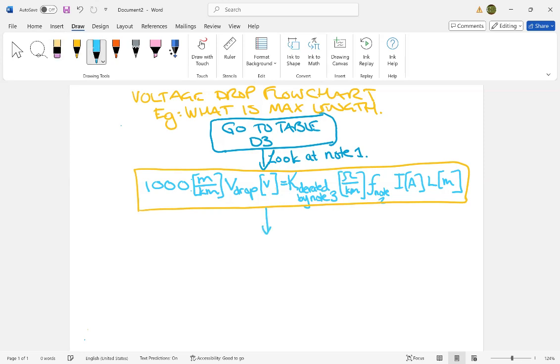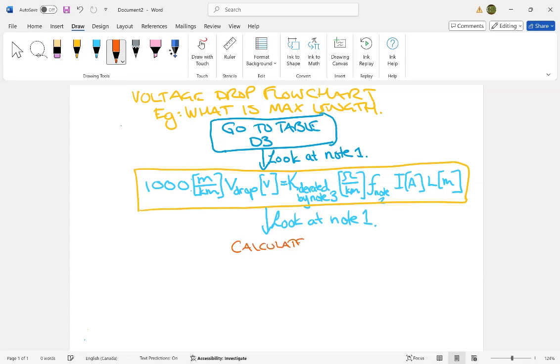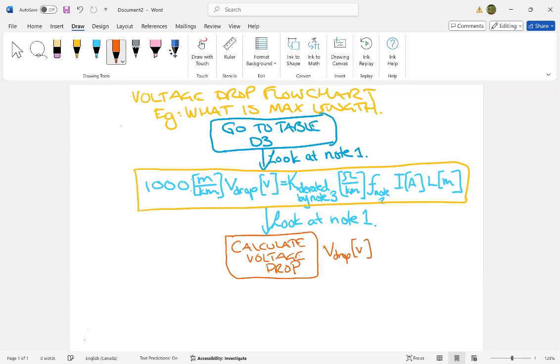All right, now I am going to look at note 1, so I have this formula, then I'm going to look at note 1, and that's going to help me calculate voltage drop. All right, so from note 1, it shows you how to calculate voltage drop, and what it says is that the voltage drop in volts, which I see right here, V drop in volts is equal to the voltage of your problem or your situation in volts times the drop, which is measured in percent, and I'll just give you an example. It might be something like this.